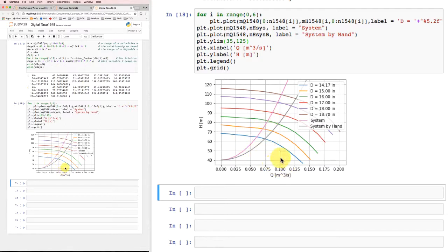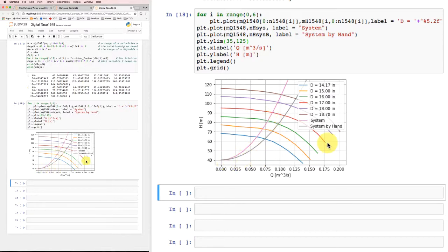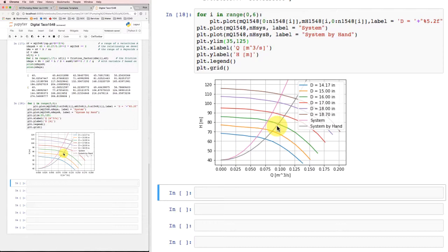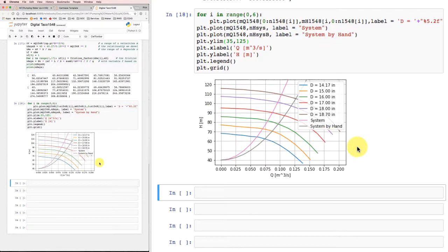And if I'd bought the 16 inch, I'd be getting only about 0.08 cubic meter per second flow rate now. So I can adjust that valve. And what that does is it takes my system curve and makes it steeper and steeper so that using that globe valve, I can adjust for whatever flow rate I want out of the pump that's lower than what it would deliver if the valve was wide open. So that's the practical outcome. And I can now start to simulate what would happen in my design if I changed my operating parameters.